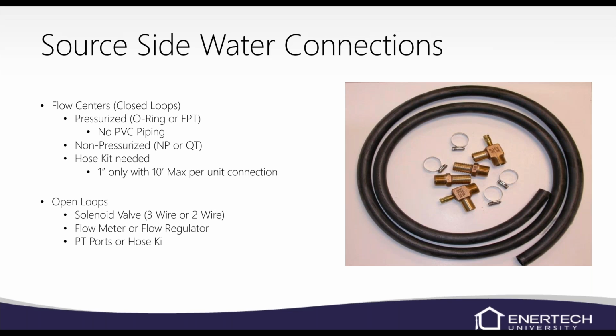And then the flow centers on the closed loop, basically the pressurized and the non-pressurized, the new ones that come out now, they're all double O-ring fitting. We do have some QT flow centers, the white flow centers out there in the field now from B&D, that have the threaded or the swivel connection, like the hose connection on them. But all the others will more than likely need the hose kit. The hose kit is a 1-inch rubber hose. You can see it in the picture there. 10-foot max per unit, so 5 foot to the flow center from the unit and 5 foot back from the flow center back to the unit.